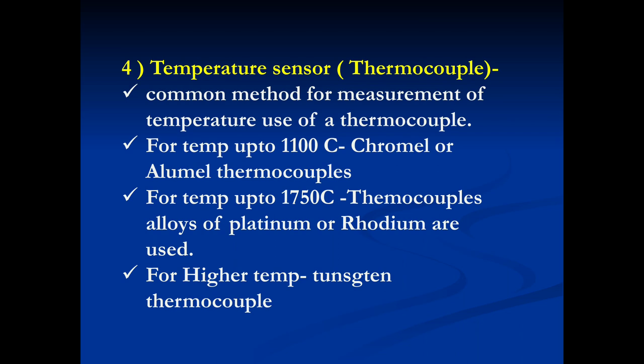For temperature up to 1750 degree centigrade, thermocouples made of alloys of platinum or platinum-rhodium are used. For higher temperatures, tungsten thermocouples are used.